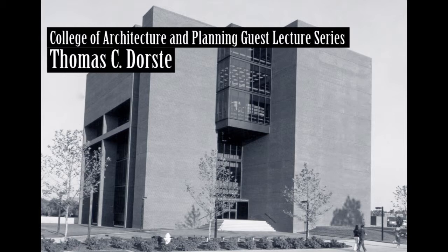The net effect is, as near as we can tell, we have cut energy costs from 1973, where we had double duct systems, reheat systems, two-pipe and four-pipe cabinet unit systems. We've reduced the energy use to about 50% of what we were doing at that point in time. And I think it's an evolutionary process, and you keep learning, and I think we can reduce it even more. There's only one other thing I want to point out.